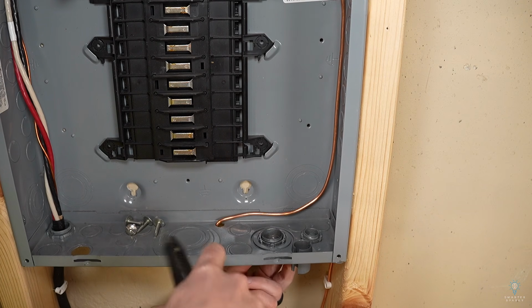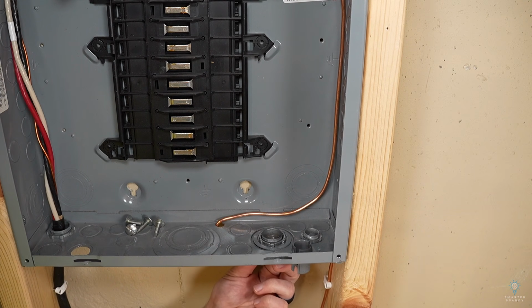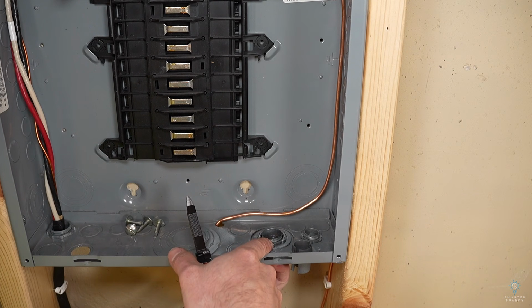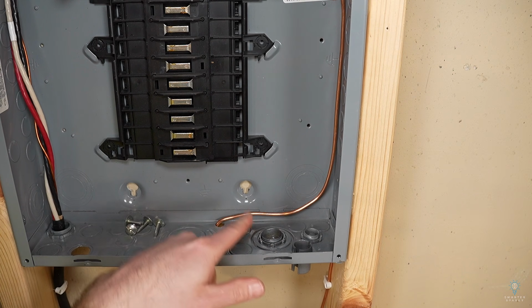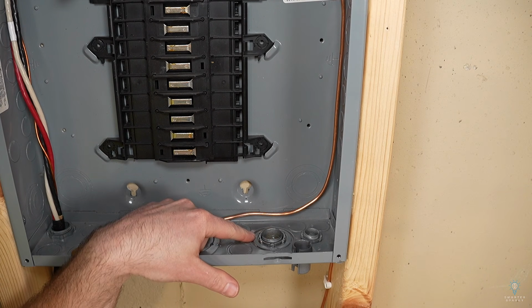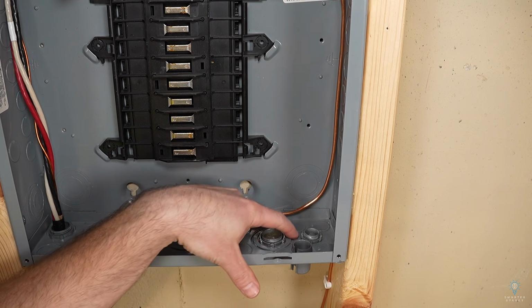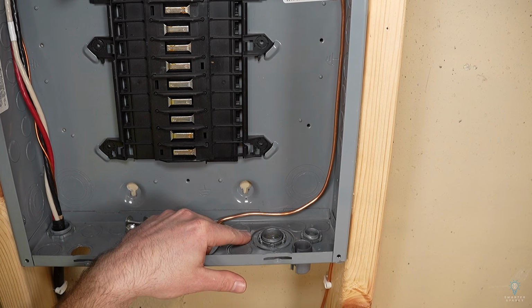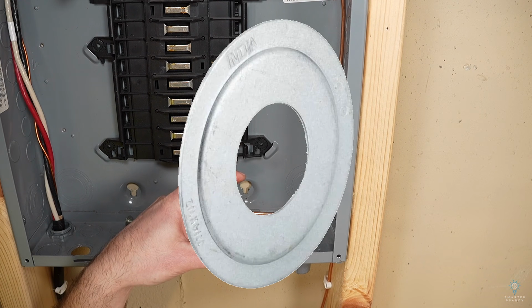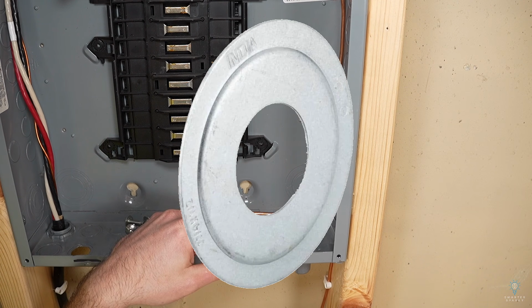Notice how this whole concentric knockout area started to move. We got to be careful we don't wrench on this so hard we break that connection there. If you do break that out, and let's say you break this out to a 1.5 inch hole, they do make reducing bushings that you can use. They're basically big washers that you can use to re-bridge that gap.